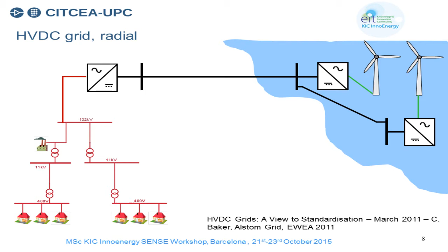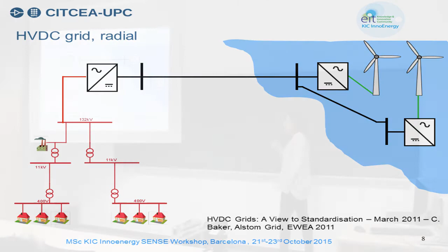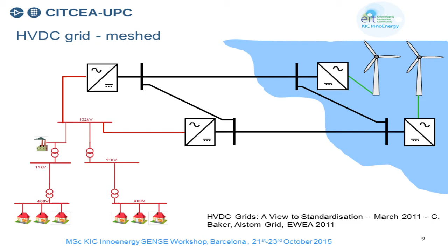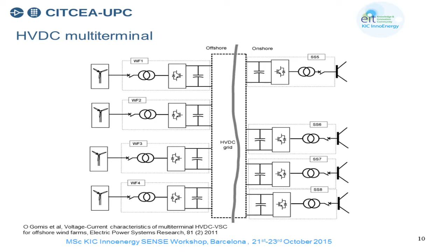Another type of configuration would be to interconnect, through the DC side of the converter stations, two wind farms. This will be the radial connection. And why not add certain redundancy and form an HVDC grid, or meshed configuration, so that if we lose one of these DC links, for example this one or this one, we can still transmit the power to the grid? So the most complex HVDC system we will have is multi-terminal, and it's even more complex if it's meshed.